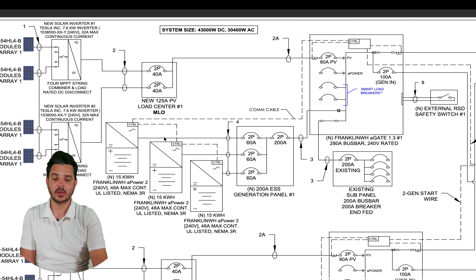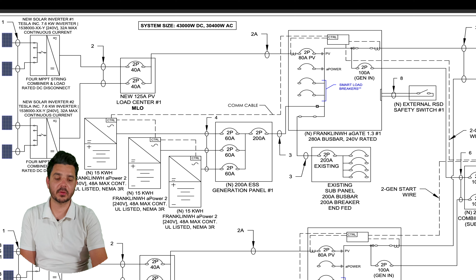And then the batteries kind of repeat this pattern, except they're higher current. So we have 3 batteries to a 200 amp sub panel, and each one is 60 amps, and that is going to go to the backup extended lugs for this type of configuration. So Franklin has a breaker slot, but that's rated for only 2 Franklins. When you go above 2, you need to use their backup extended lug, which then goes where the backup loads feed, right? So very straightforward.